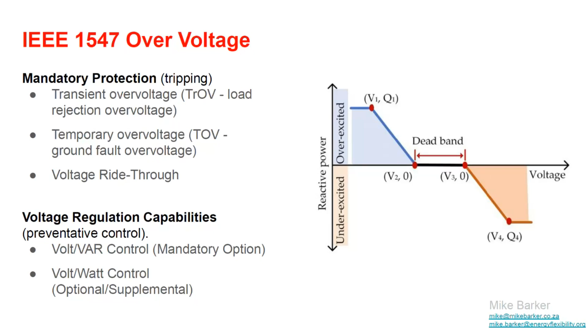If you think of it this way, this approach of 1547 is treating the source of the problem. Now we hear a lot of discussion about how you can resolve these issues by putting in extra devices on the feeder, even some sort of clever advanced tap changer on the transformers, or rotating machines to provide inertia. 1547 says that's fine, but let's have a look at the source. Let's have a look at each individual inverter, and how can they be good grid citizens and work together to protect the feeder, to protect the grid?